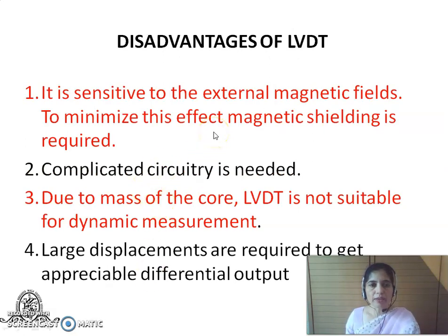Disadvantages of LVDT are it is highly sensitive to external magnetic fields. The reason is any external magnetic field would induce additional voltage in the two secondary windings, and therefore it might not reflect the displacement accurately. So if the effects of external magnetic fields have to be minimized, then one has to provide magnetic shielding, which would be an additional arrangement required for this particular device. Also, because of the mass of the core, LVDT is not suitable for dynamic displacement measurement.